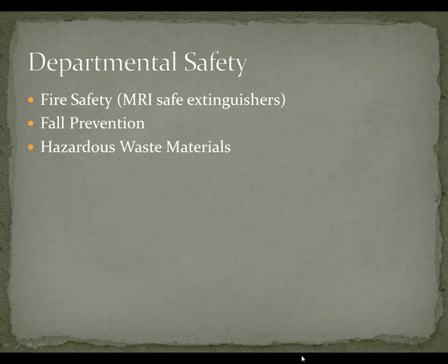It is important that you, as the MRI technologist, know what equipment is MRI compatible, and equipment that is not compatible should be clearly marked. Any equipment that may need to enter the MRI suite in case of an emergency must be MRI compatible. Oxygen tanks, wheelchairs, and stretchers should be made of aluminum. Sharps containers and hazard waste bins should also be MRI compatible and made out of plastic or cardboard.